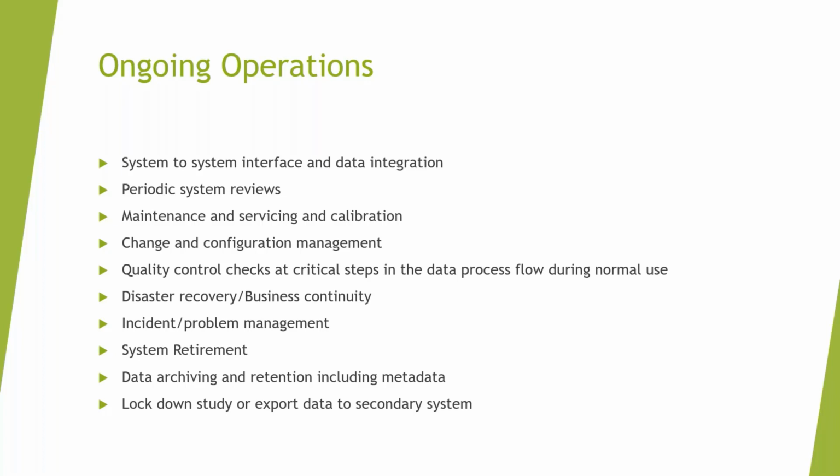The change and configuration management, i.e. what ongoing user management systems are in place? Are there patches and system upgrades that have been completed, and are they tracked, controlled and documented? What quality control checks at critical steps in the data process flow during normal use have been put in place? Are they sufficient? Are they at every area? Is there sufficient disaster recovery and business continuity measures put in place, i.e. what's the system going to do if it loses power mid-analysis? Is there an incident problem management process in place? Is there something that defines how people oversee any incidents that occur?